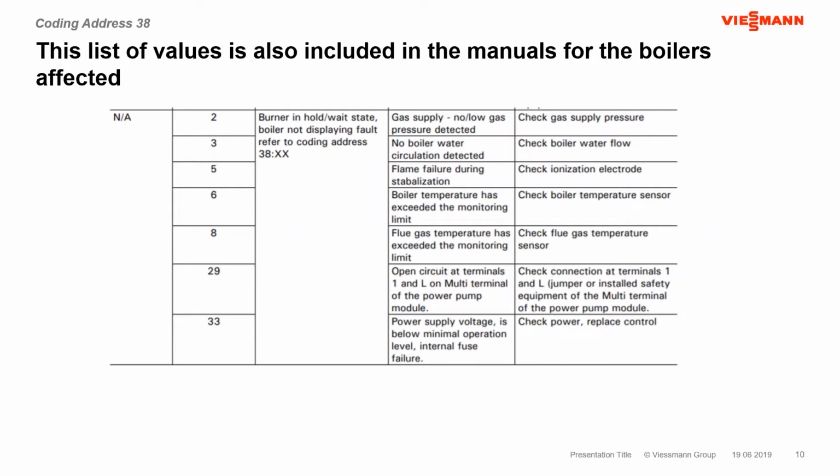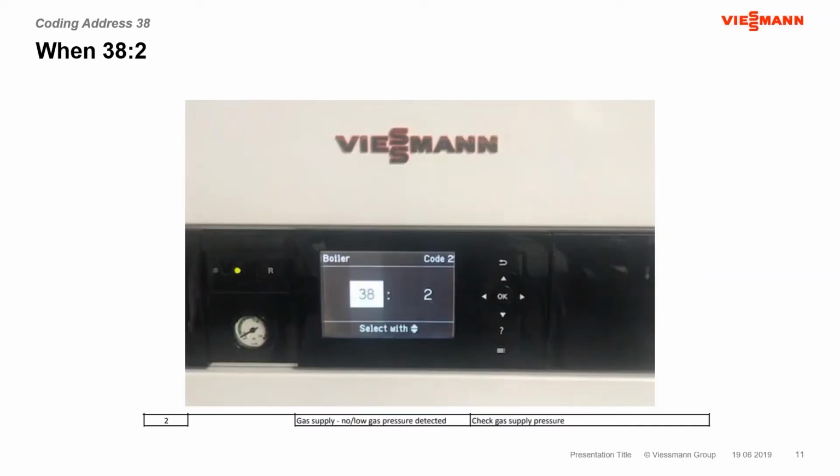And if you open up the troubleshooting portion of the service manuals, at the very end of the different faults, you'll have this list of these particular faults that don't actually cause the red light to illuminate on your burner control. So these are detailed in a couple of different areas.